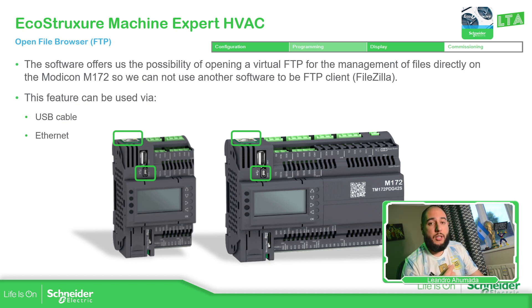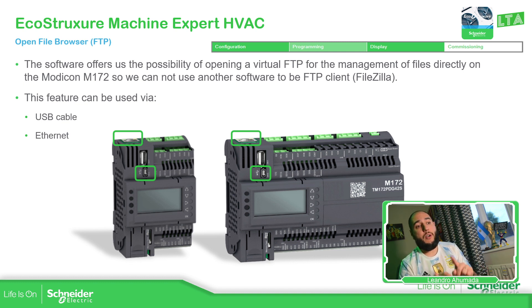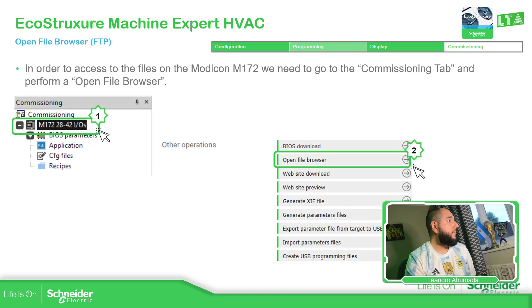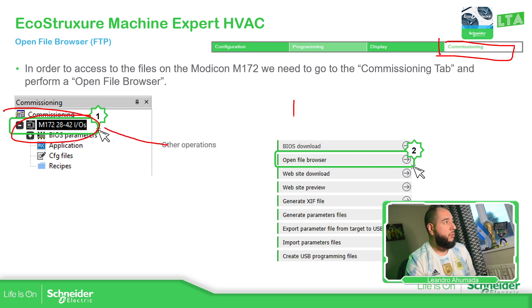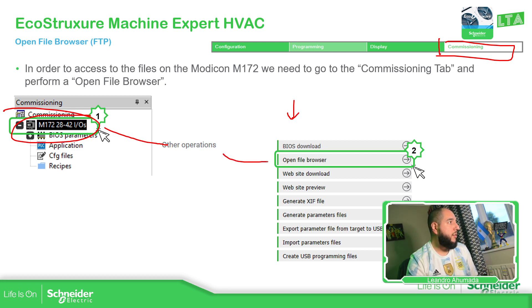If you're using an external FTP client, you will need to use the credentials — the username and password that you have for the controller. If you use the software tool inside Machine Expert HVAC, there is no need for that. What we need is to go first to Commissioning, then select the controller on the commissioning window, under Other Operations. We need to scroll down in the options and then we should be able to see the File Browser.